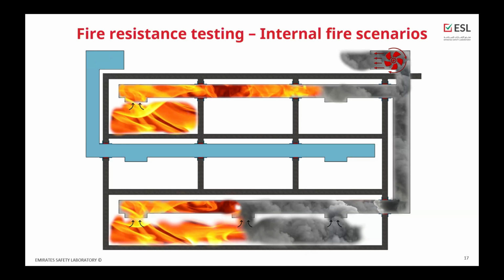This is called fire inside the duct, and the duct must contain the fire inside and not allow it to spread to the other compartment, either through the duct construction or through the penetration seal system. On the bottom of this graphic, you can see the situation presenting a single compartment duct. The difference between those two is that the single compartment duct removes the smoke directly outside the building and serves only one compartment.